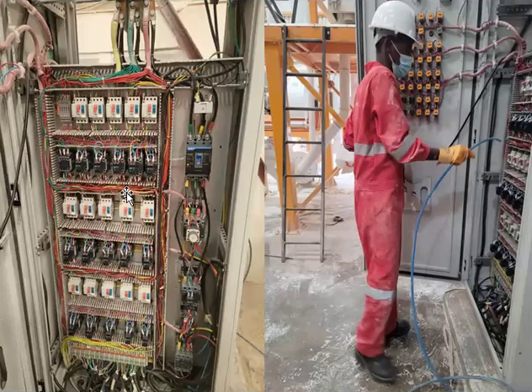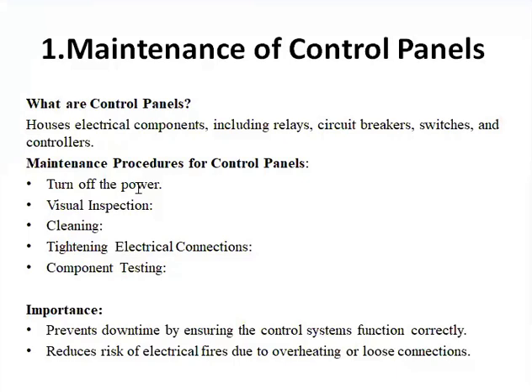So you have to always clean the panel. Make sure it is very clean. You also clean each component there. Each component, separately, like we always clean these contactors. We open them and clean the contacts. We schedule it maybe every 3 weeks, but you should always do it monthly. Open these contactors and clean the contacts. So we always tighten electrical connections. This is to fight against loose connections, and loose connection is a very big problem in control panels.